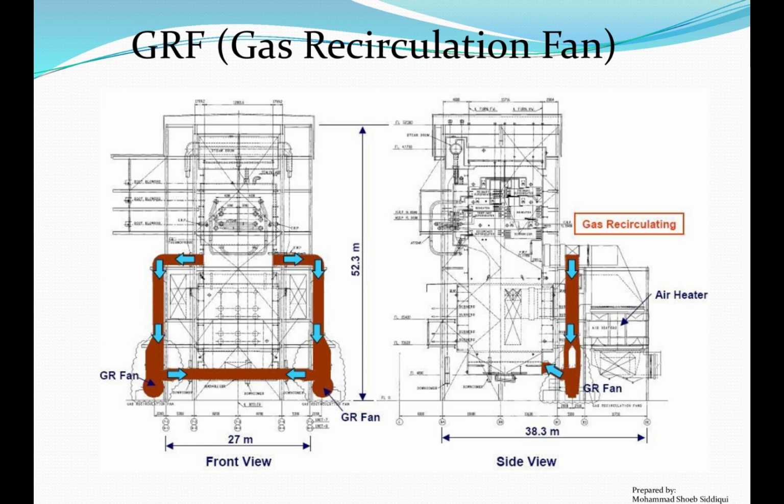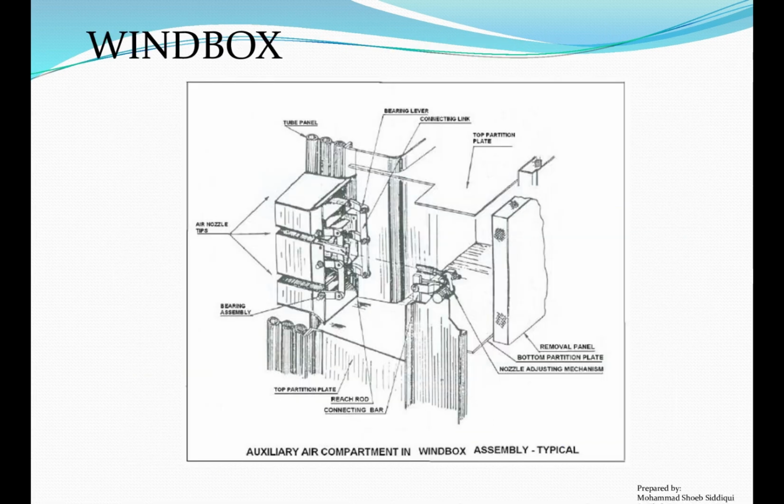RH outlet steam temperature is normally controlled by regulating the gas recirculation flow. Increased flue gas flow over the reheater convection heating surfaces increases the heat absorption, and RH temperature is increased. GRF is also used to reduce NOx formation by reducing peak flame temperatures in conventional applications.